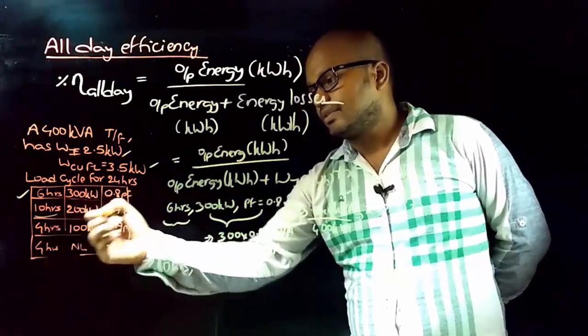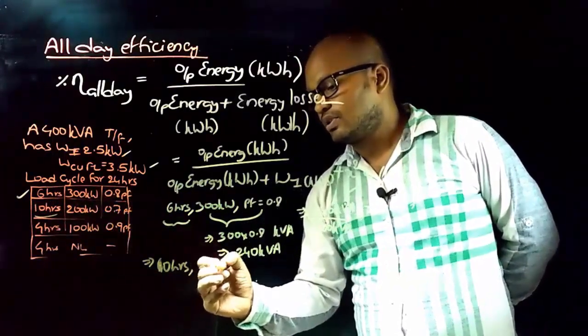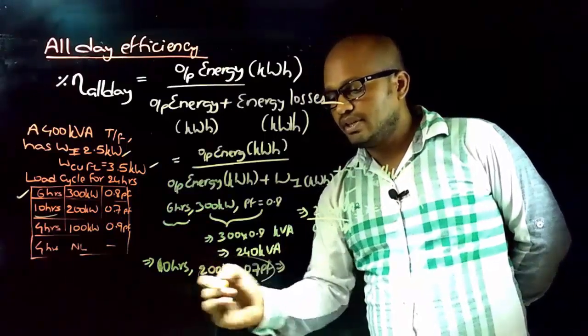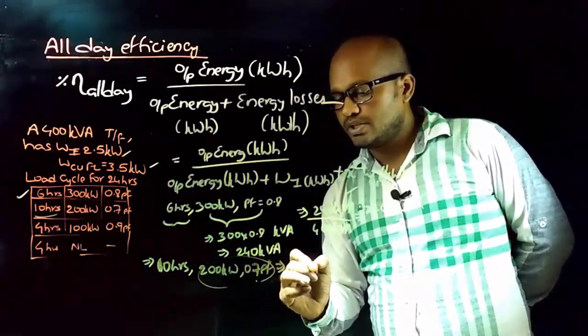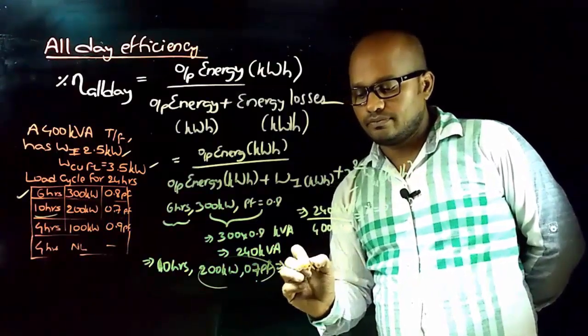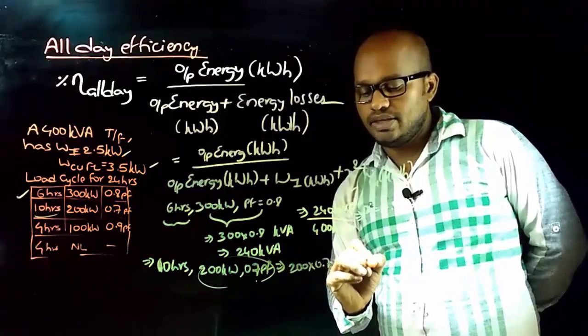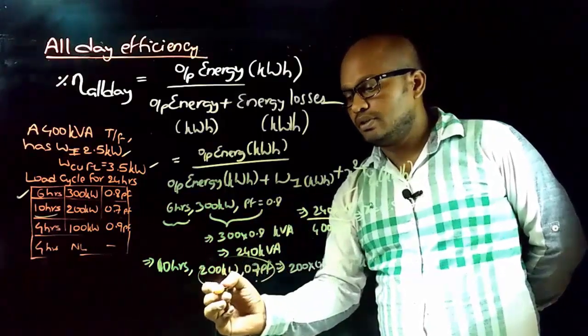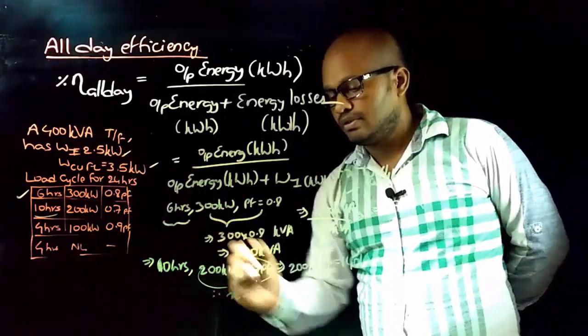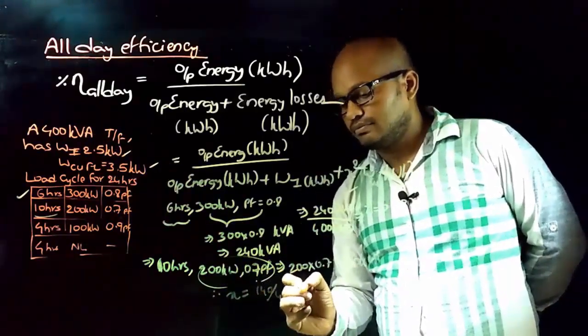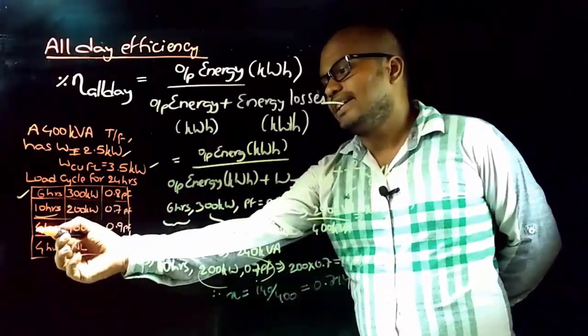Similarly, for the next 10 hours, the transformer output is 200 kilowatts at 0.7 power factor. Multiplying 200 by 0.7 gives 140 kVA. Therefore, the loading on the transformer is 140 divided by the transformer rating, which equals x = 0.714.